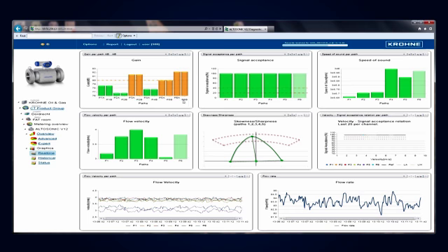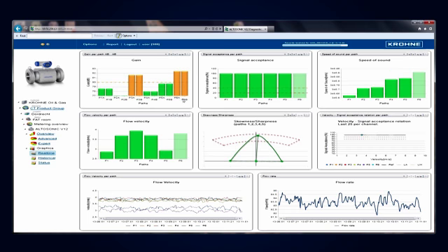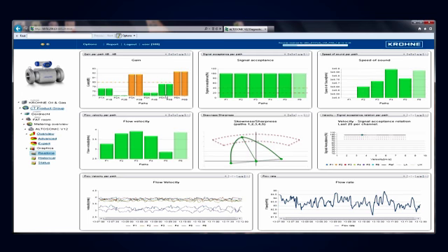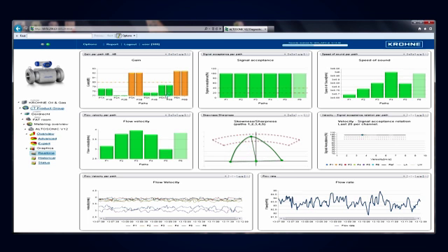3 and 6 are high because of the low pressure in the meter. The meter runs at atmospheric air, so the longest paths, 3 and 6, will have slightly high gain. Path 5 just went to green again. A little bit high, nothing to worry. It has to do with the atmospheric conditions under which this meter runs.